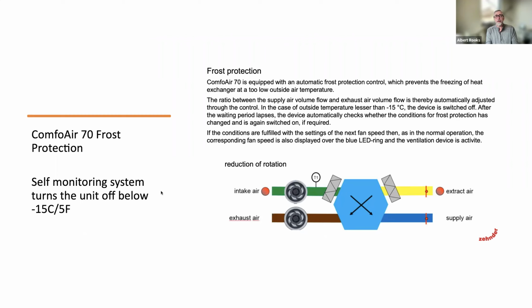Frost protection for cold climates is managed in this system. It's a smart system, so it knows what the temperature is at all 4 points, and it's got a little motherboard and so forth, so it's always doing an assessment and a calculation. And essentially, when the outside conditions get down to -15°C, which I think is around 5°F or something like that, or about -5. So if it's an HRV and it's not very smart, essentially what it's going to do is borrow some of that warm exhaust air and give it back to the core and bring it back on the supply side, which is something I'm not really a fan of. Because you're essentially taking your bath exhaust and running it into your supply flow to warm the core, but you're giving air that you're trying to get rid of back into the building in your supply flows, whereas there are just better ways.